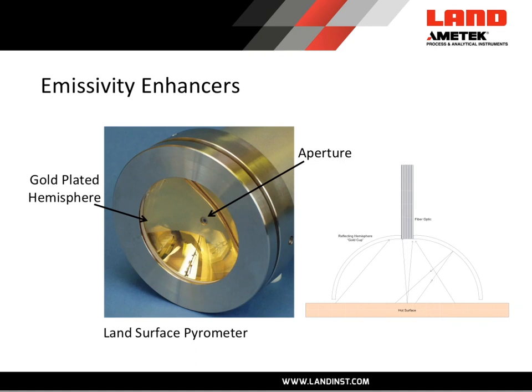If there isn't a cavity you can make one. This device is known as an emissivity enhancer, and these are widely available fitting onto the front of radiation pyrometers. In cross section you have a gold plated hemisphere — that gold plating is extremely highly reflective, causing emissions from the surface to bounce around inside that sphere. They integrate together and finally escape through a very small aperture at the top of the hemisphere onto a detector and are measured, so you can bring the emissivity value up to a very high value close to one.